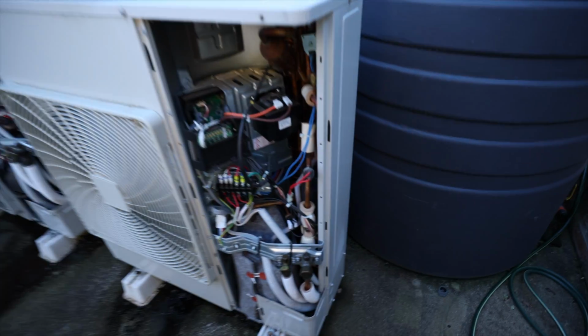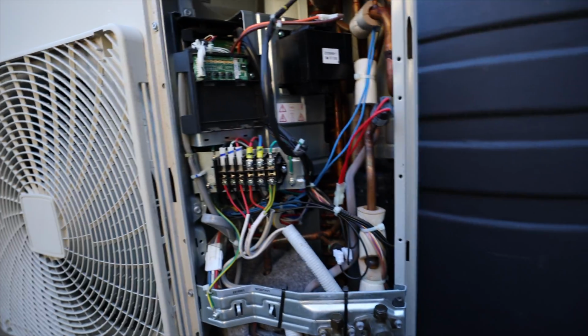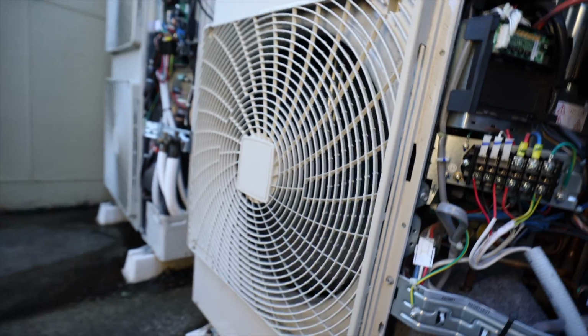So back into heating mode, and pipes are starting to warm up again, this one. That's where the hot gas is sent to the indoor. At the moment, the indoor coil will still be heating up. Once it heats up and reaches 35 degrees, then the fan, it's a DC fan motor, so it starts pulsing on slowly. But this is now back into full stride of heating, fans running flat out, compressors ramping up, air off.